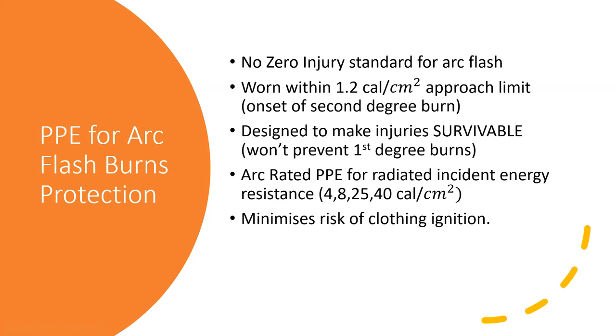One of the main purposes of PPE is to minimize the risk of clothing ignition, because often the arc is extinguished once the breaker clears the fault. But once the clothing is ignited, the victim could be on fire for some time. And that's what 80% of electrical burns damage seems to be caused by: clothing ignition.